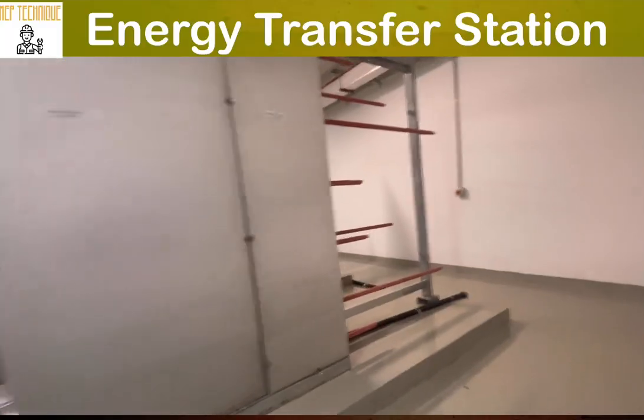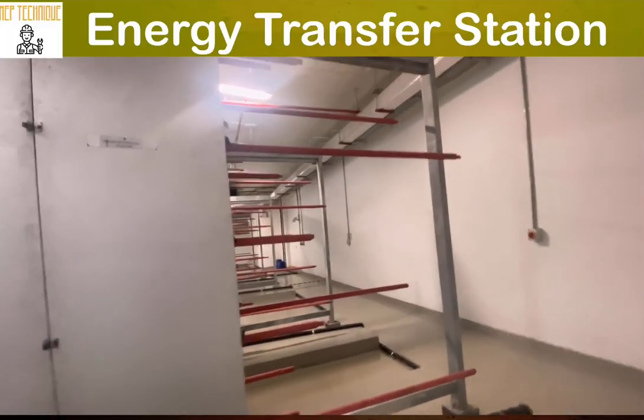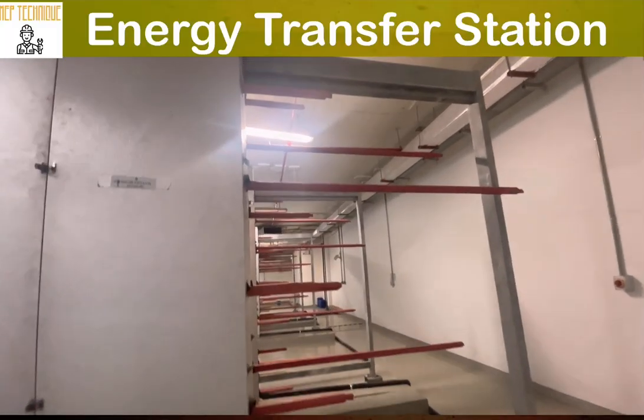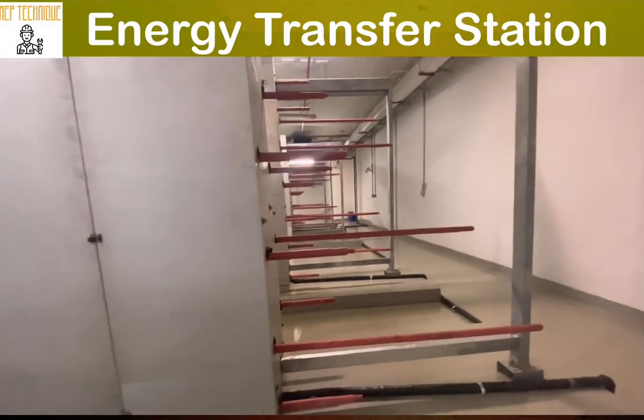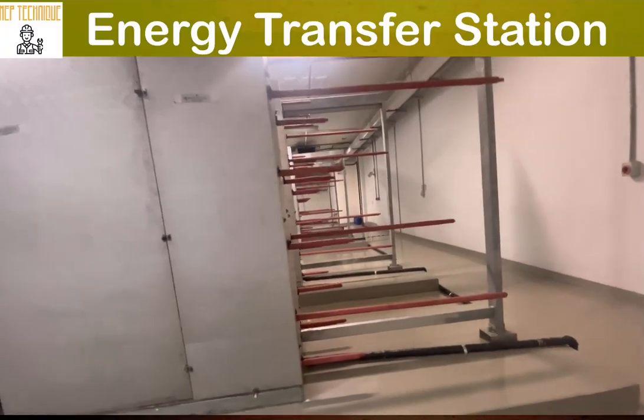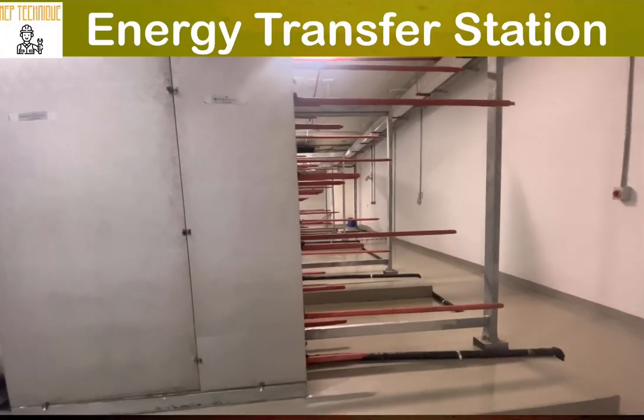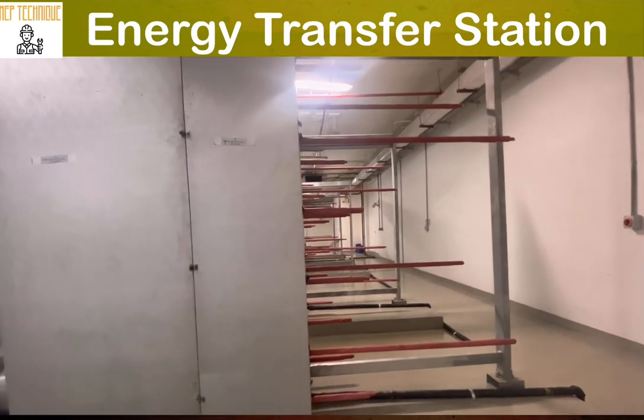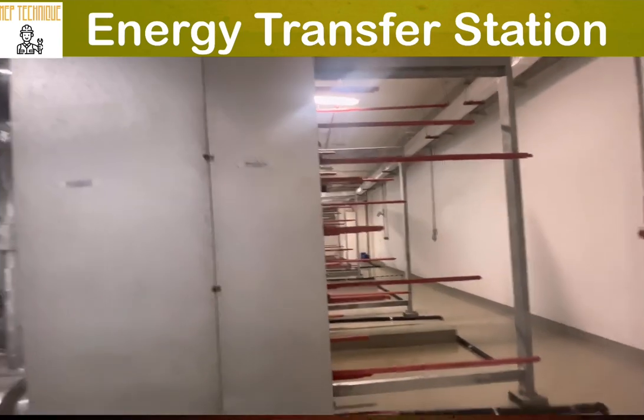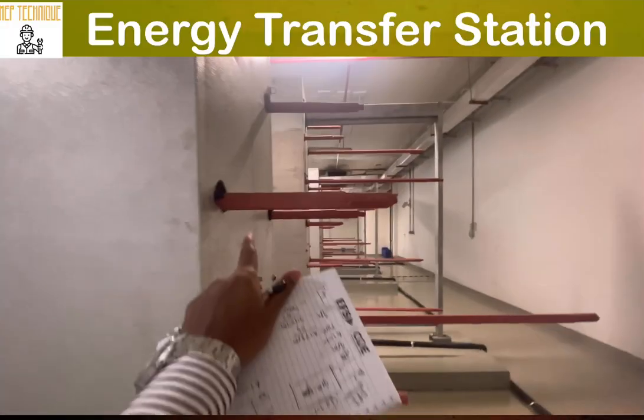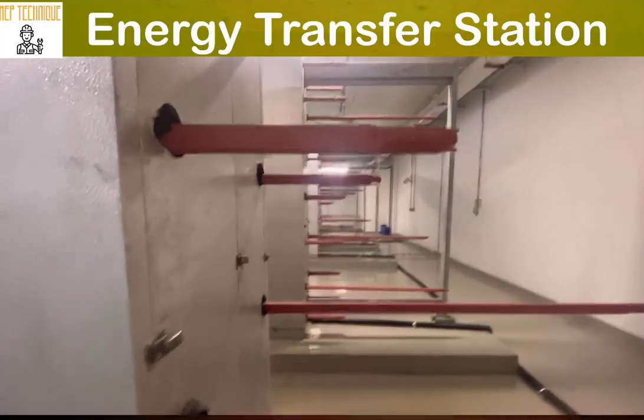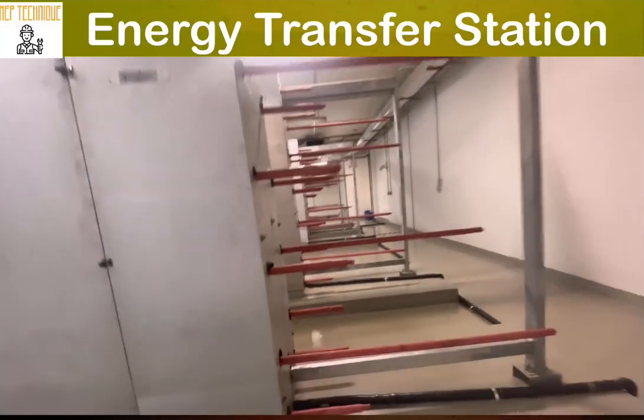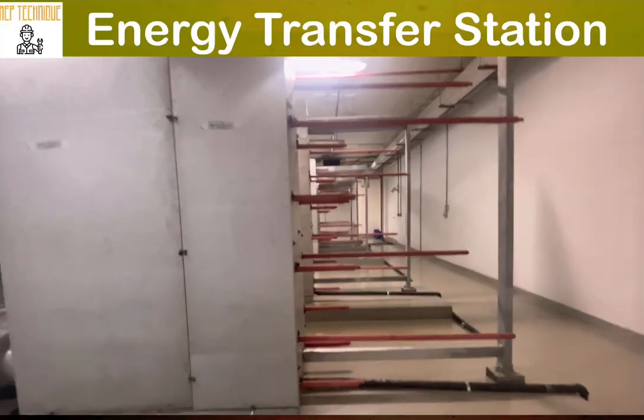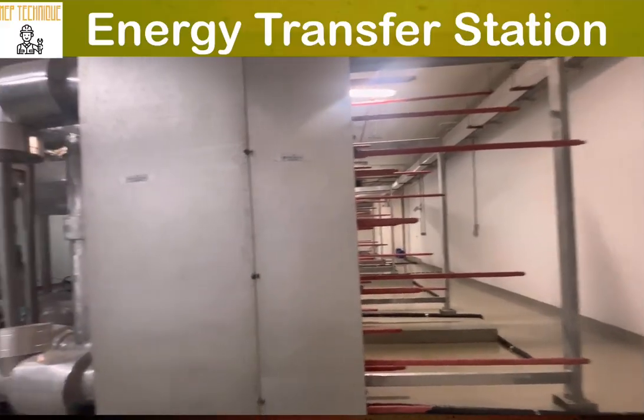In the plate heat exchanger you can see there are some red color extension rods here. So what is the purpose of these rods? As you know, one of the advantages of a plate heat exchanger is that in future you can add plates to improve the capacity. That's why you can see the extension rods here. In future we can add plates to increase the total capacity of the heat exchanger.